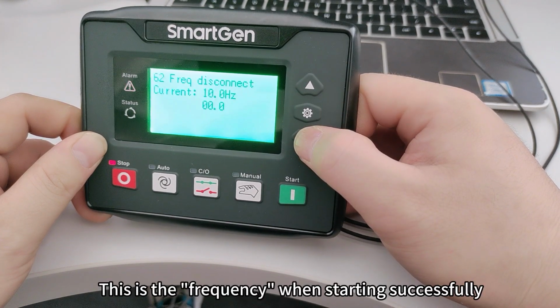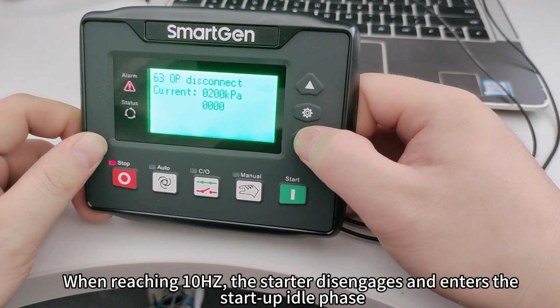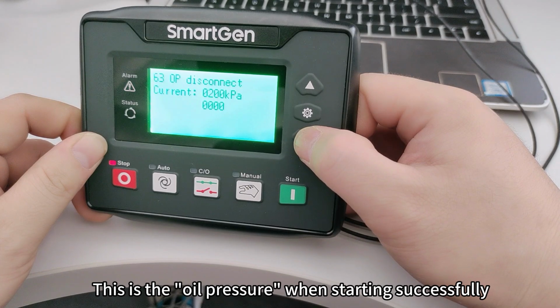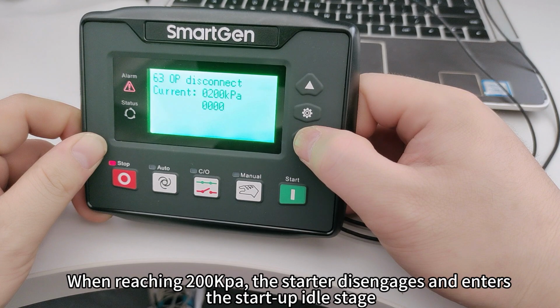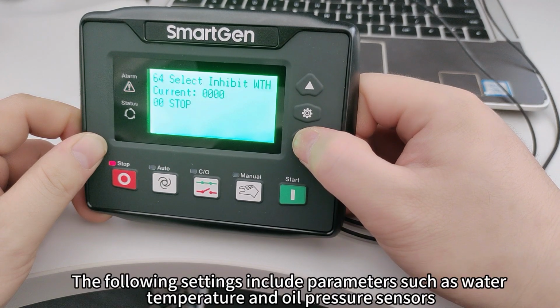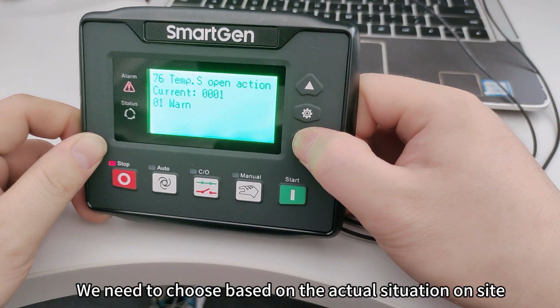If it is the frequency for starting successfully, when reaching 10 Hz, the starter disengages and enters the startup idle phase. If it is the oil pressure for starting successfully, when reaching 200 kPa, the starter disengages and enters the startup idle stage. The following settings include parameters such as water temperature and oil pressure sensors. We need to choose based on the actual situation on site.